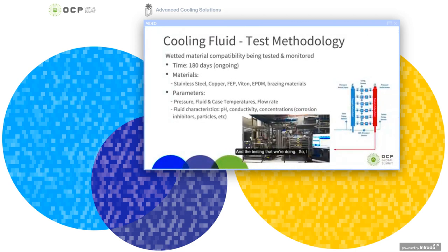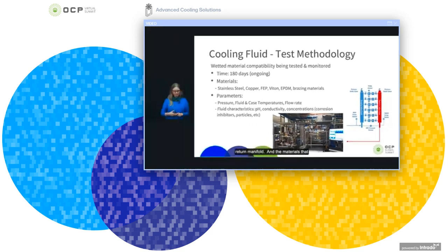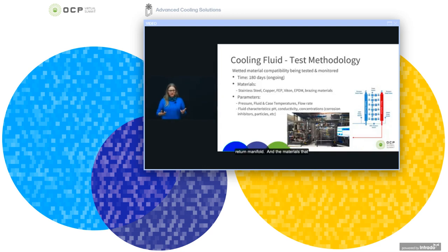And the testing that we're doing, I said that we're having ongoing testing, and we've been testing for 180 days now. You see a picture on this slide from the lab where we have the test setup, and to the right, you can see a sketch of what that test setup looks like. So you have a supply manifold that goes into a quick disconnect. Then you have two cold plates in series. And the fluid is going out through the quick disconnect into the return manifold. The materials that we have in this fluid loop are stainless steel, copper, FEP, Viton, EPDM, and brazing materials. So this is the testing that we're currently doing now.